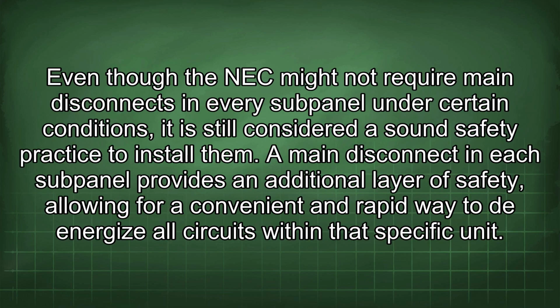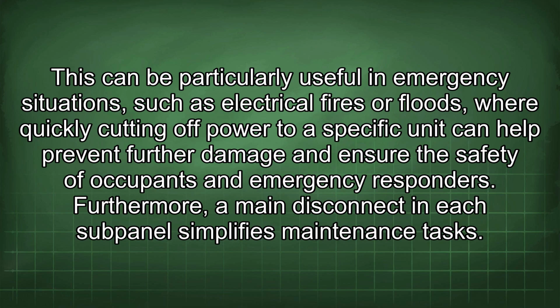Even though the NEC might not require main disconnects in every subpanel under certain conditions, it is still considered a sound safety practice to install them. A main disconnect in each subpanel provides an additional layer of safety, allowing for a convenient and rapid way to de-energize all circuits within that specific unit. This can be particularly useful in emergency situations such as electrical fires or floods, where quickly cutting off power to a specific unit can help prevent further damage and ensure the safety of occupants and emergency responders.